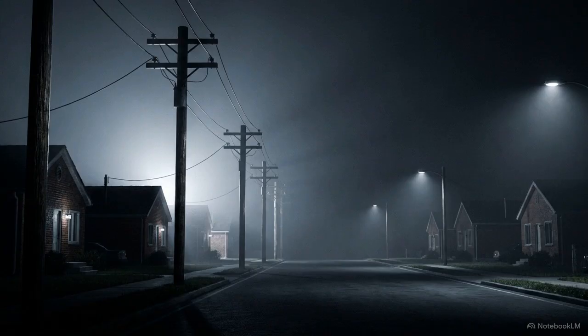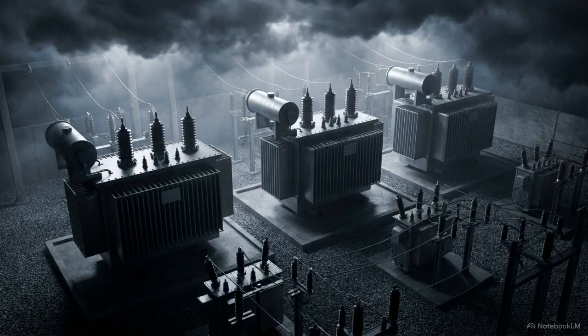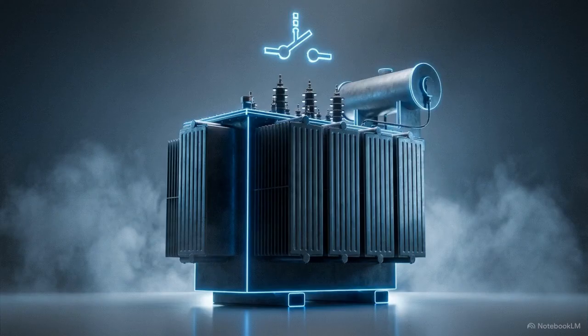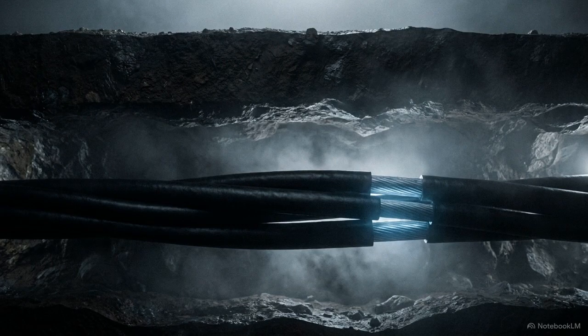Fortunately, you rarely see this happen on a typical day. Ferroresonance demands a specific set of environmental and operational factors aligning all at once. The first requirement is an unloaded or very lightly loaded transformer that remains connected to a system with high capacitance. A long underground transmission cable is a prime example of this kind of capacitive source.